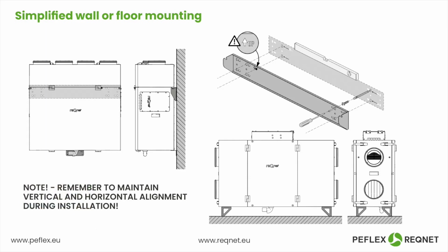Why is this so important and crucial? Yes, because, among other things, the wall or floor installation of recuperators from the Recu series is important due to the need for proper vertical and horizontal alignment. There have been cases where water leaked from the drip tray, not draining through the siphon with the condensate, but instead escaping somewhere to the side. Precisely because the device was installed crookedly, not level.